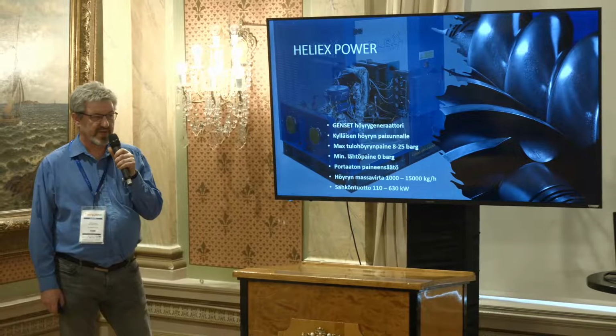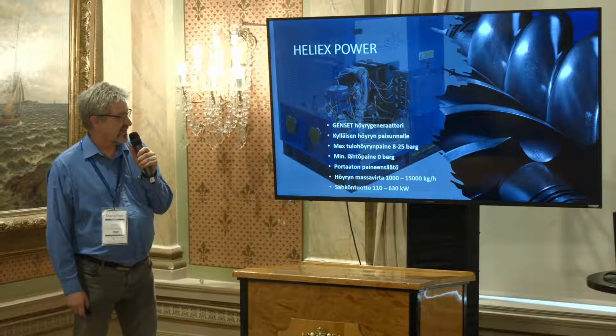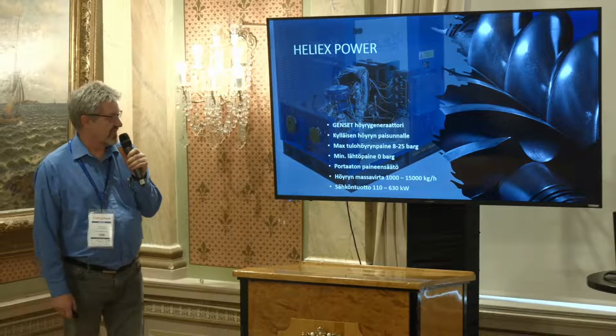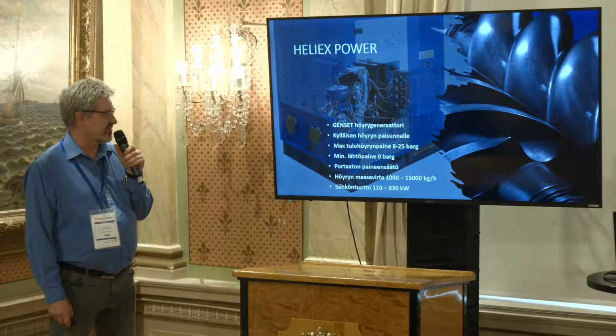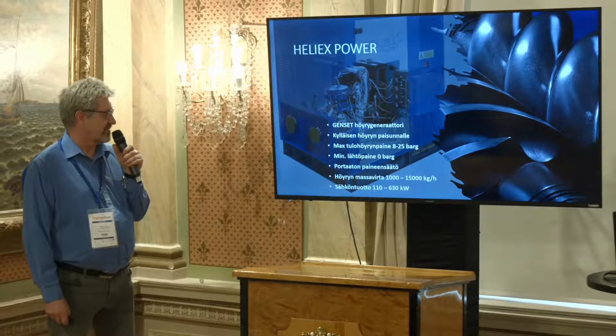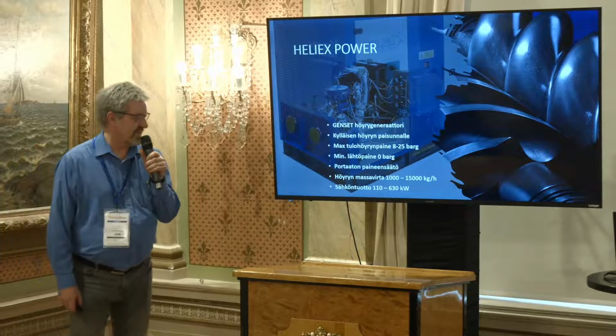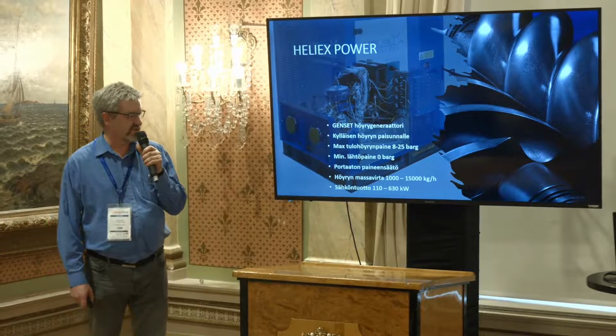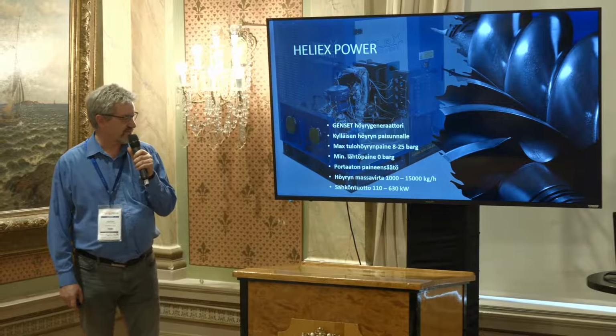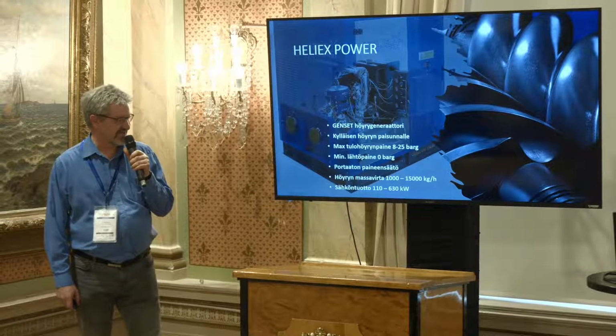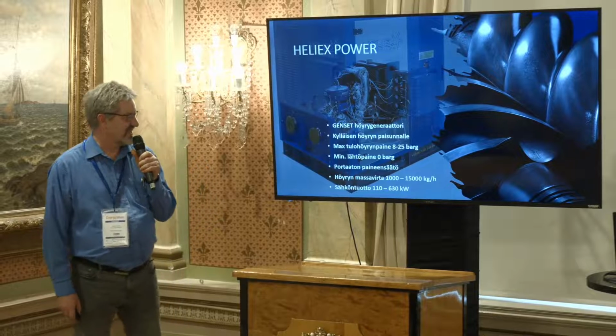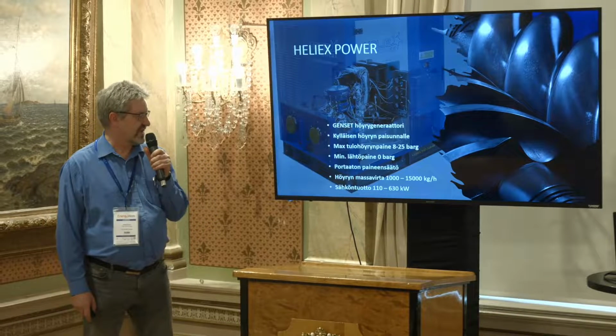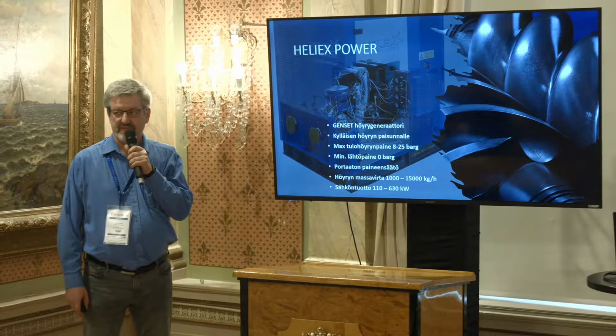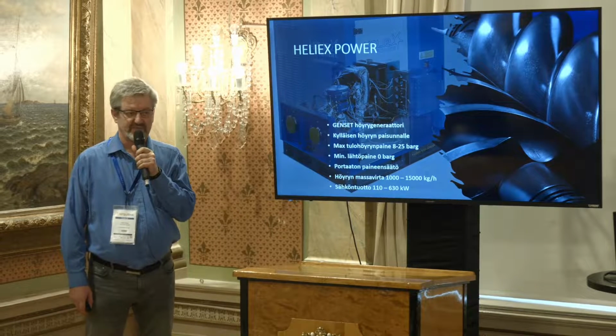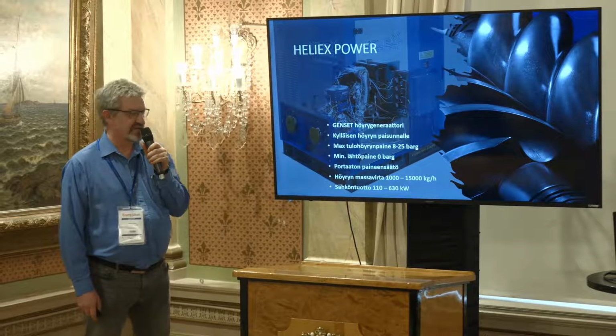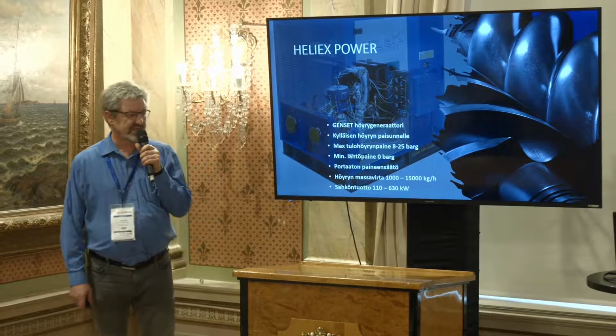We can control it, or we can adjust the outgoing power, and maximum steam flow is 15 tons per hour. And electric production is 110 to 630 kilowatts. So this is not a main turbine of the power plant. It's really designed to replace reduction valves.